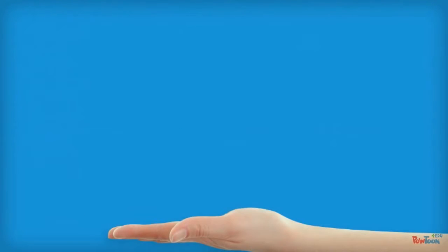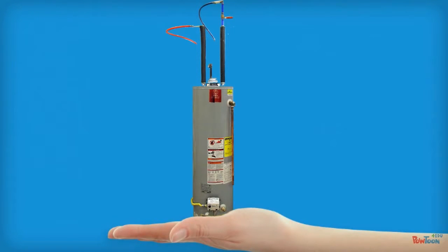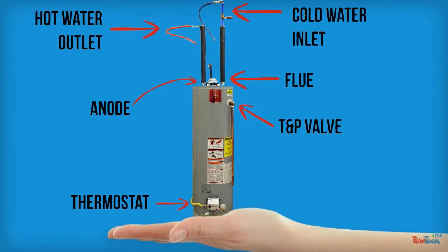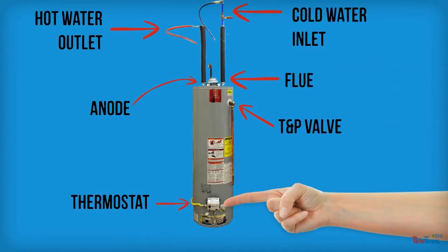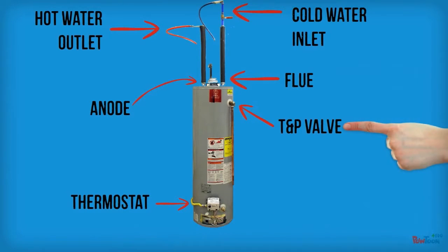The different parts and functionalities matter, because if I have to work on the tank and I know how the parts function inside there, that's going to help me troubleshoot. Instead of going through 20 different items, I can pinpoint maybe two of them and say it's going to be either this or that. So it's regulated by a thermostat. If the thermostat's out, then I'm not going to have hot water. Or if the T&P valve's out, then I'm going to have super hot water because it's not regulating the temperature inside there. So that's why.